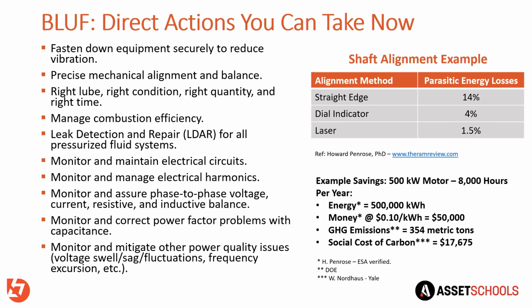He said, what if I told you that fixing that with a passive filter would reduce your energy consumption by 12%? I'd say, I think that you're trying to argue for perpetual motion. You're making energy. He said, yeah, that's what I thought too, until he saw it. What's happening is when you have energy on your ground and neutral, it goes back to your transformer and causes distortion in your transformer. So it's not the energy that's on the ground and neutral, it's what it does to your transformer that has the great impact. So I would encourage you, just take a multimeter out and check your amperage on your ground and neutral.